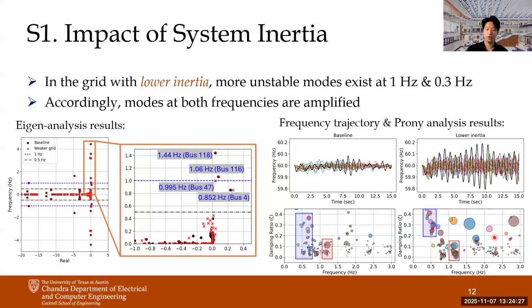And the interesting point comes from the figures below, which are the Prony analysis results. The x and y axes of these figures show the frequency and damping ratio of the measurements at each bus, and the size of the circles represents the magnitude of the oscillation. When we compare the left and right figures, you can first see that there's a larger oscillation at 1 Hz in the lower inertia system. There are also larger oscillations in the lower frequency zone around 0.4 Hz. But the interesting point here is that in the lower inertia system, these lower frequency modes have a higher damping ratio, because of the impact of the reduced inertia.